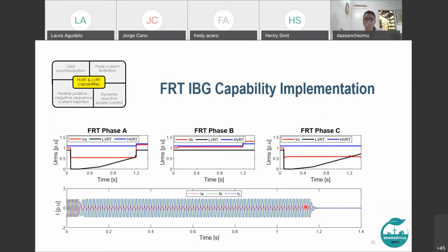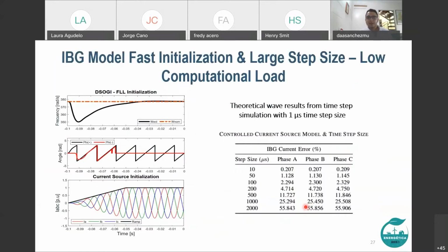So the fault ride-through implementation and consideration is essential because we expect renewable power plants to stay connected under fault conditions, supporting the system and the protection schemes, clearing these fault events before fault ride-through capabilities are overpassed. Okay, and this is the last one.